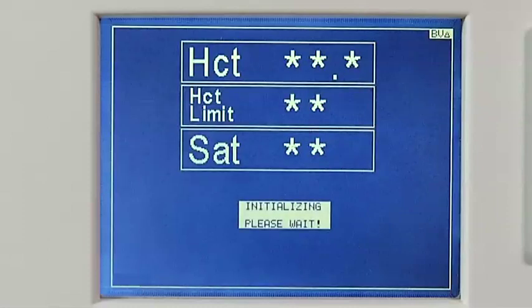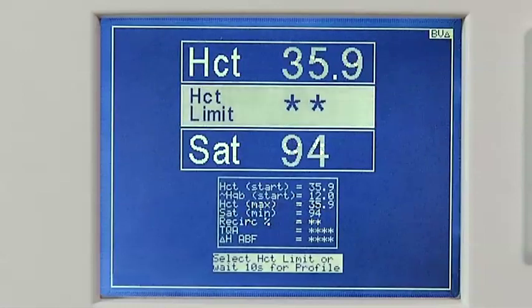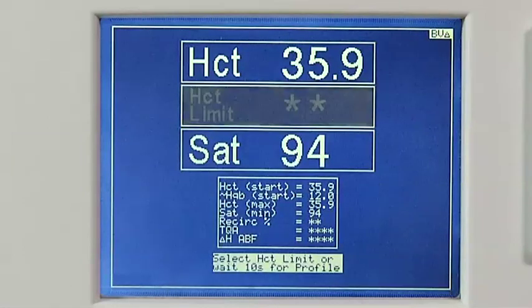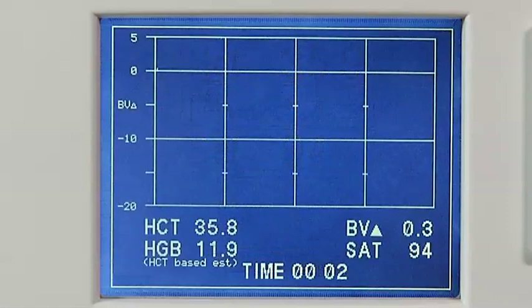The startup screen can be accessed at any time during the treatment by pressing the menu button one time. The startup screen will appear for 10 seconds before returning to the blood volume screen. This screen is used to enter a hematocrit limit and also to remind you of the patient's beginning hematocrit and hemoglobin. You can also use this screen to see the maximum hematocrit measured during the treatment, as well as the lowest oxygen saturation that has been measured during the treatment.